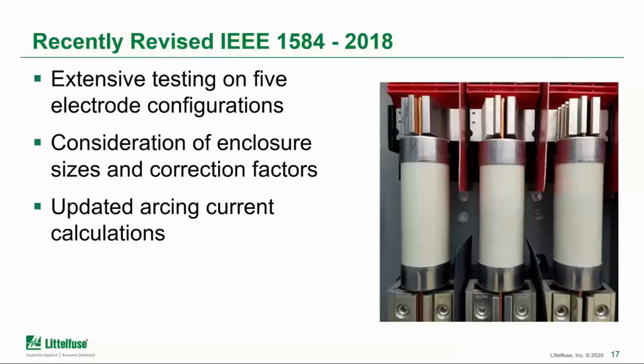In addition to the actual electrode positioning and configuration, there are enclosure correction factors that are also provided. So it really allows the formula to adjust the incident energy based on the enclosure opening. The standard enclosure opening is 20 inch by 20 inch, and the maximum value provided is 49 inch by 49 inch. So the formula doesn't completely change based on the volume, but ultimately it reduces the incident energy for the larger openings, as that energy is less tightly focused coming out of a wider opening. And if it's a shallow enclosure, that trend is also reversed.